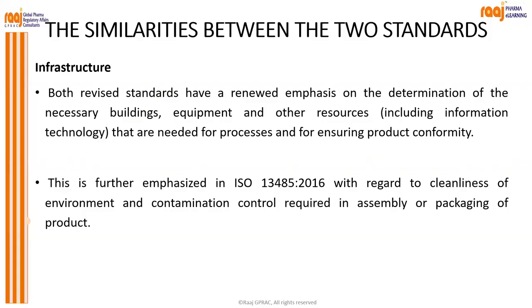But see to it that when we purchase any equipment which has a computerized system, it has to be validated. So see to it that your PCB or the computerized system, or suppose you are using ERP or any system which has the electronic part, then you get the 21 CFR Part 11 compliance certificate from your vendor. This is very important when we talk about the IT part, the information technology part, electronic part, or computerized system. So see to it that the computerized system is validated.